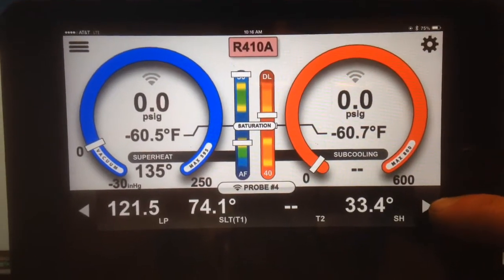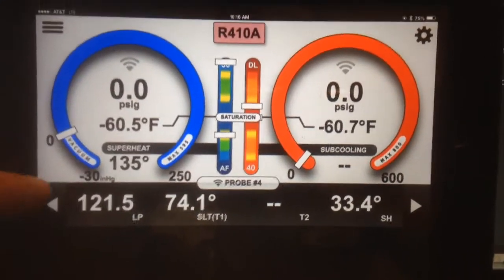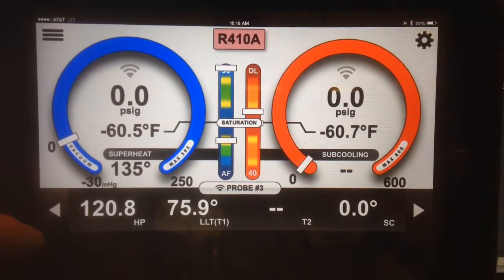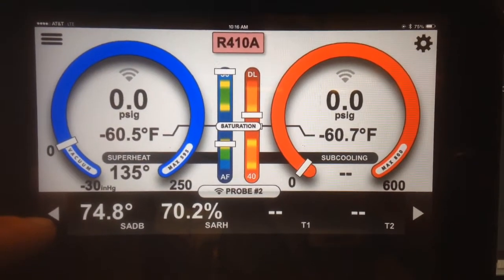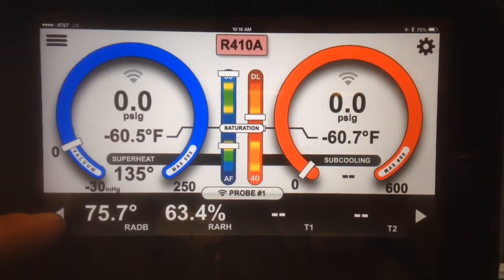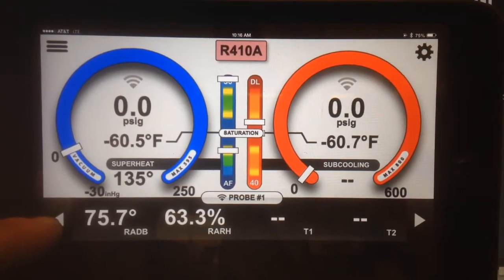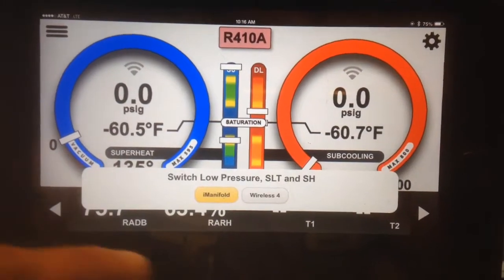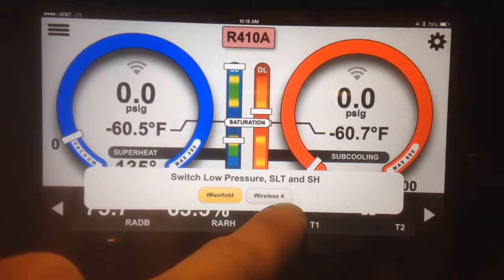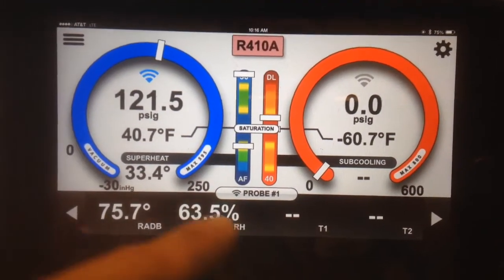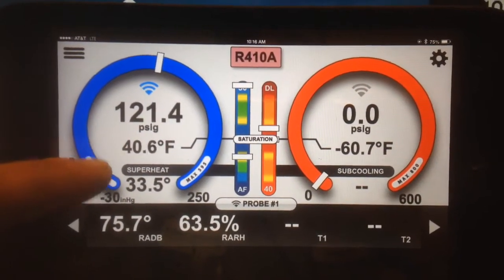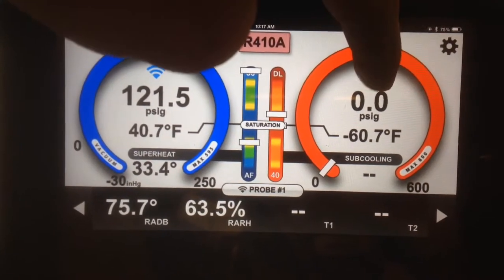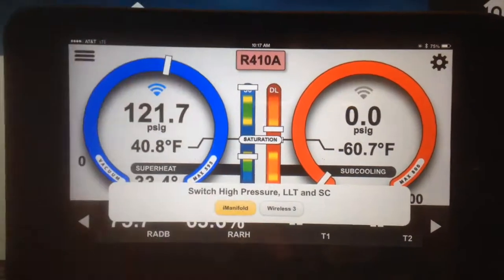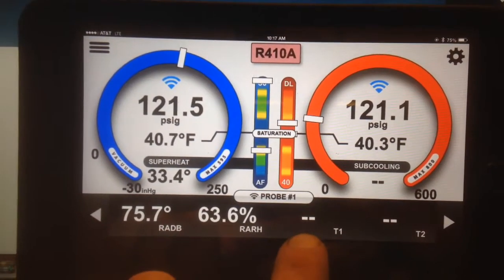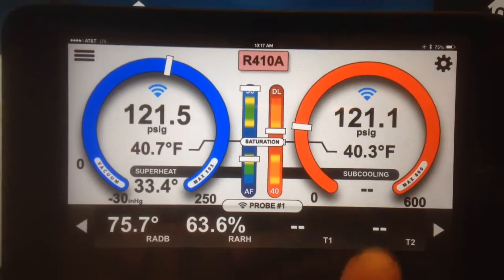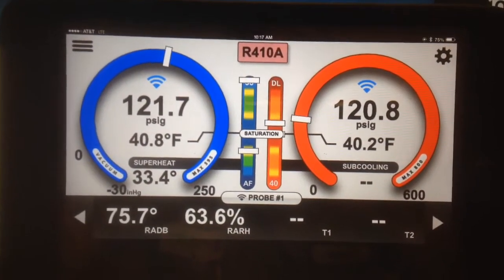LP is low pressure. HP is high pressure. Supply air, dry bulb, and return air, dry bulb. System is not running. If we come up here and touch the little Wi-Fi icon and switch from iManifold to wireless 4, we see our suction pressure, saturation, and superheat. Come over here to the high pressure Wi-Fi icon, switch to wireless 3, we see our high side pressure, saturation, and no subcooling as the system is not running.